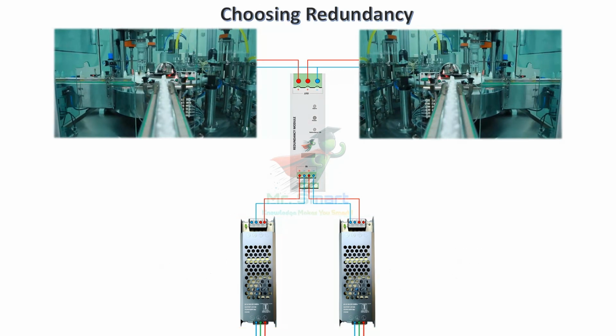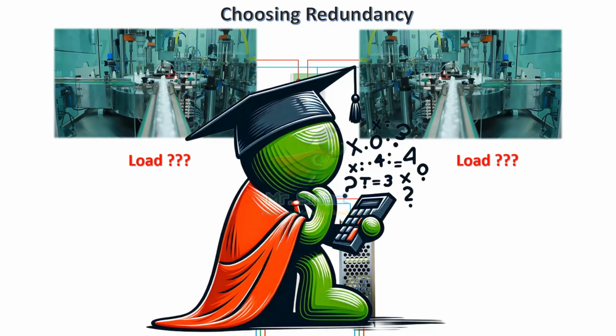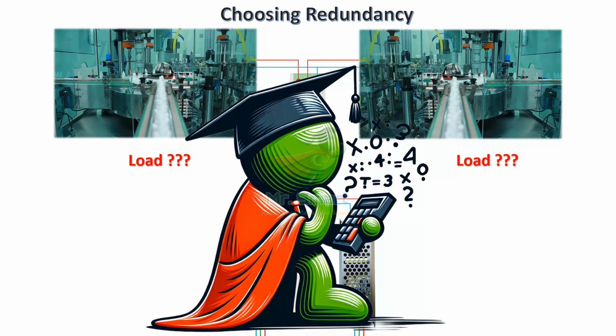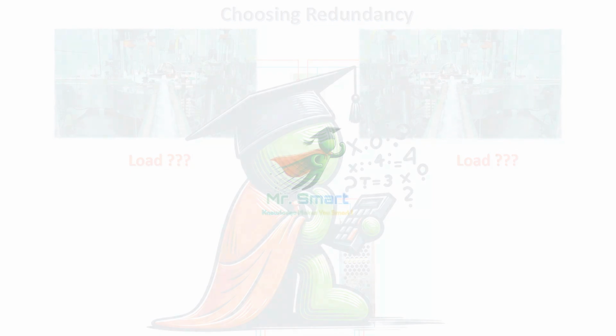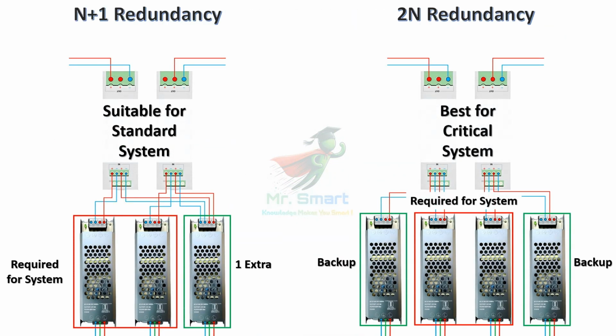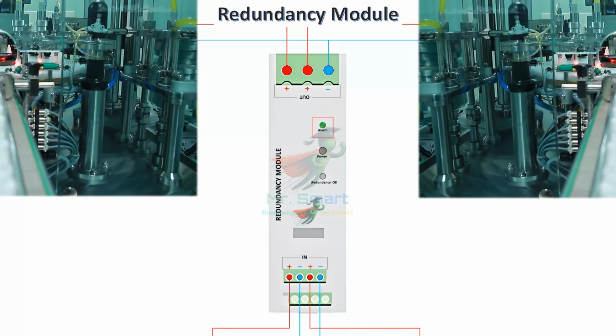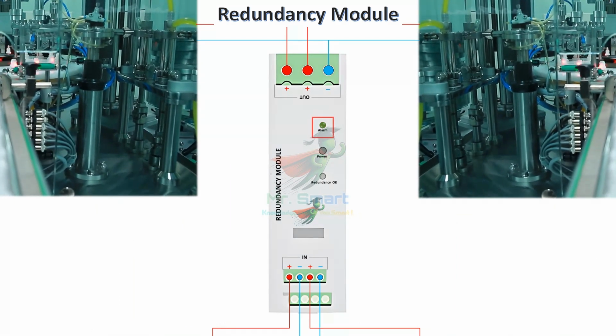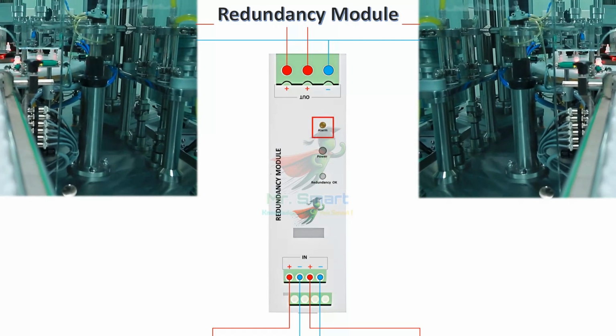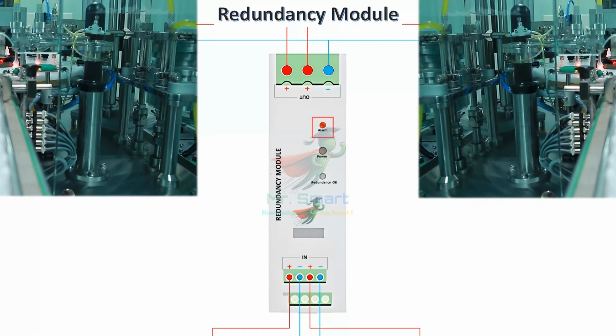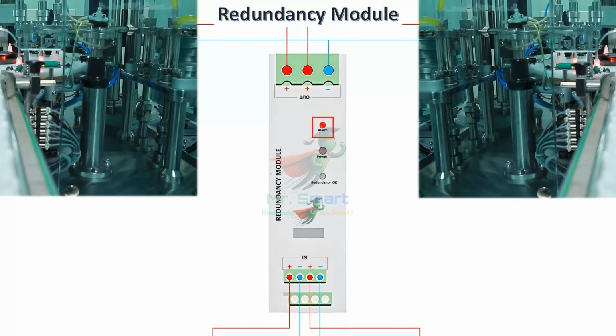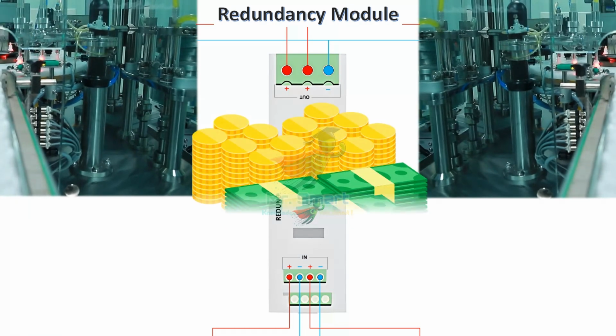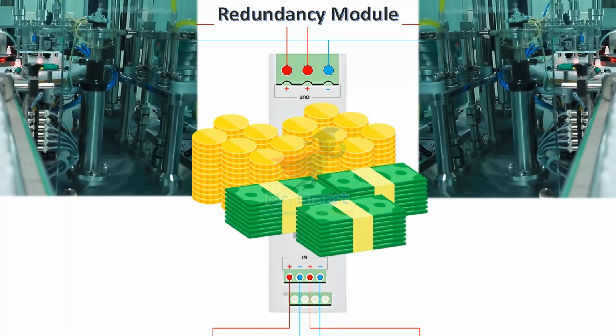To pick the right one for your system, consider some factors like power requirements. Calculate the total load of your system. Choose modules that can handle slightly more than the load. Choose N+1 for standard redundancy, 2N for mission-critical systems. Prefer modules with monitoring features. Look for systems with alarms, LEDs, and software integration for easy monitoring. And it will be better if the module has a hot-swappable design, ideal for systems that need constant uptime. And most importantly, balance the cost of redundancy with the risk of system failure and go with the best budget.